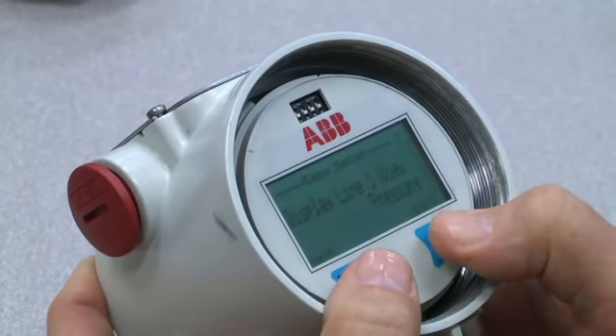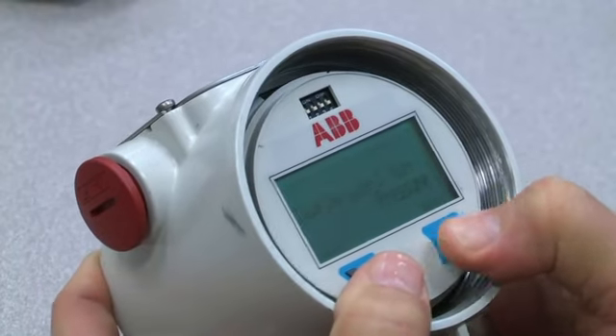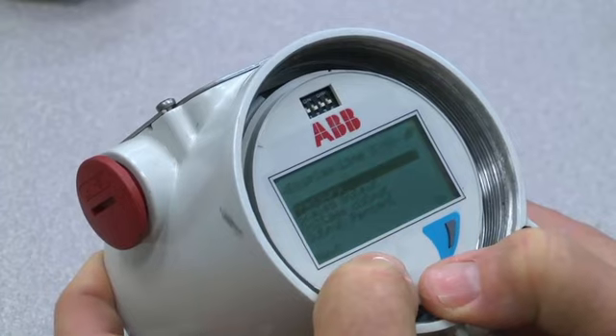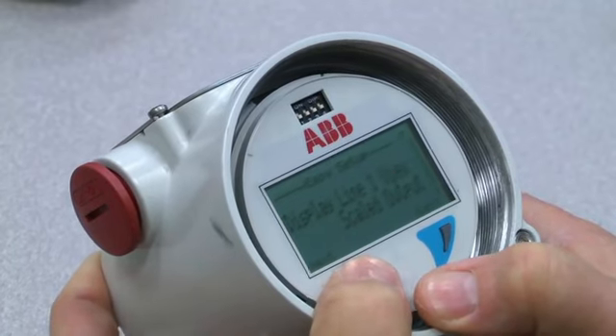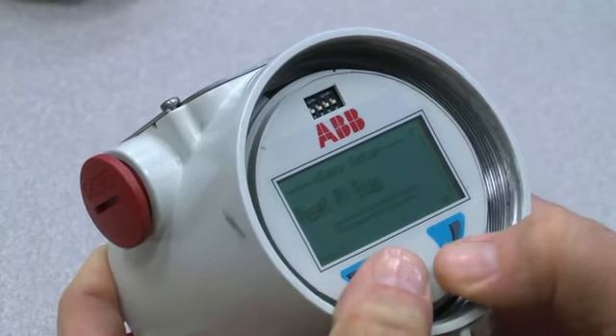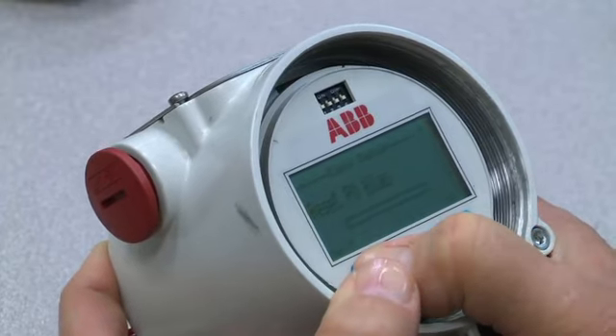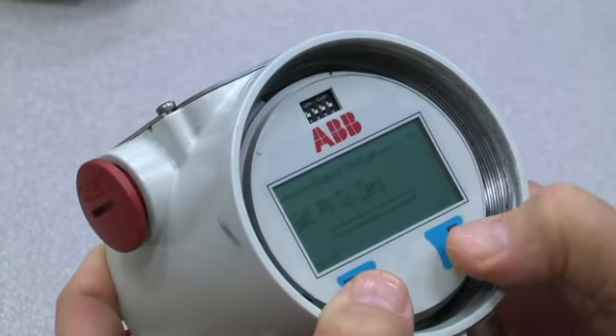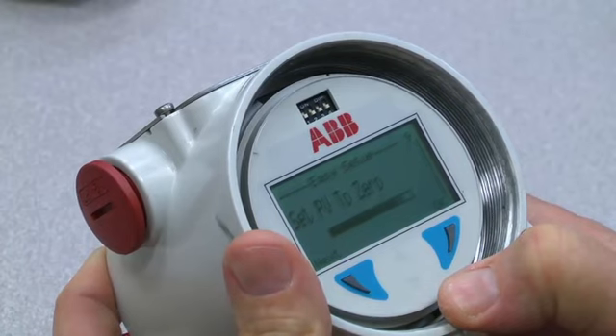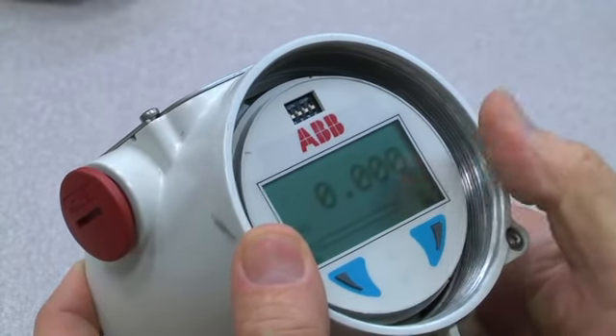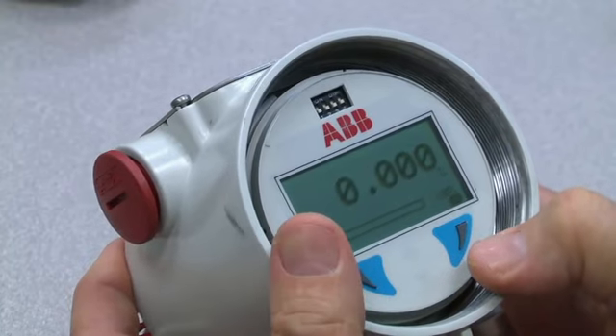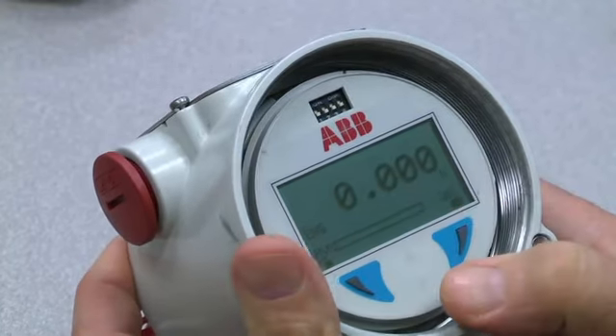The display line view, this enables you to change what's displayed on the display. So if I wanted to put my scaled output on there, I can select that and say OK. And then next. This is reset PV bias. All you have to do is hit OK and it'll automatically do that. I'm not going to do it on this one, but I am going to set the PV to 0. So I select OK, and it runs through and it zeroes it for me. And now my device has been zeroed. I go next, and then I'm out at the main window again, and then it'll automatically come out of the menu.